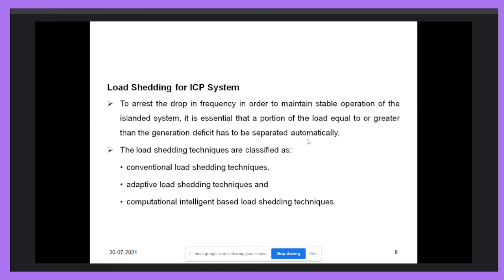Computational intelligence based load shedding techniques are adaptive and more reliable as compared to conventional techniques. They adapt to changes in the system automatically. Suppose we talk about the under frequency relay based load shedding technique: we have to provide a setting in the relay for a particular case, and that will be constant irrespective of the operating scenario. The relay will detect the frequency and disconnect the load. But in computational intelligence based load shedding, the amount of load which will be disconnected changes on the basis of the operating requirement or operating scenario.